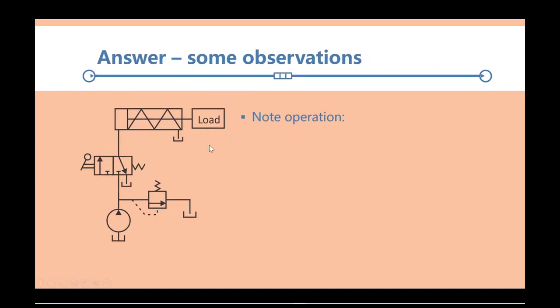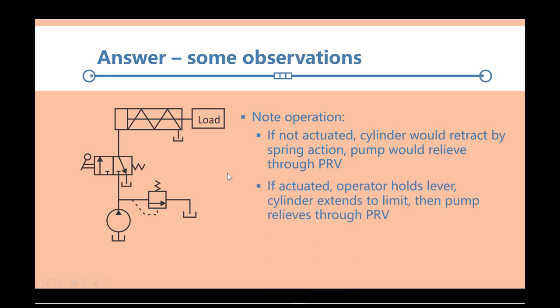Okay, now a few other things to observe here. I've said this already, if we don't actuate the valve, the cap end is connected to the tank, and the spring will retract the cylinder, it'll push on the piston, and make the cylinder retract. At that point, we're blocked here, and we're relieving through the pressure relief valve. If you actuate, then the cylinder extends to its limit, and the pump relieves through the pressure relief valve.